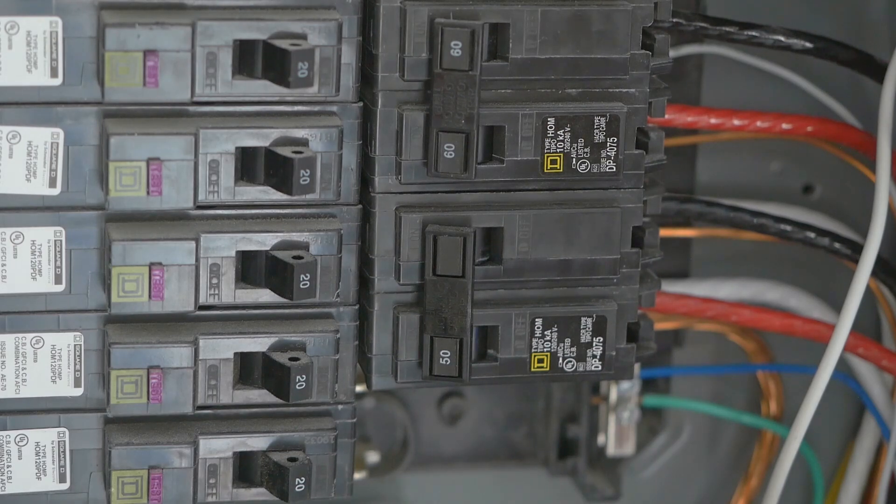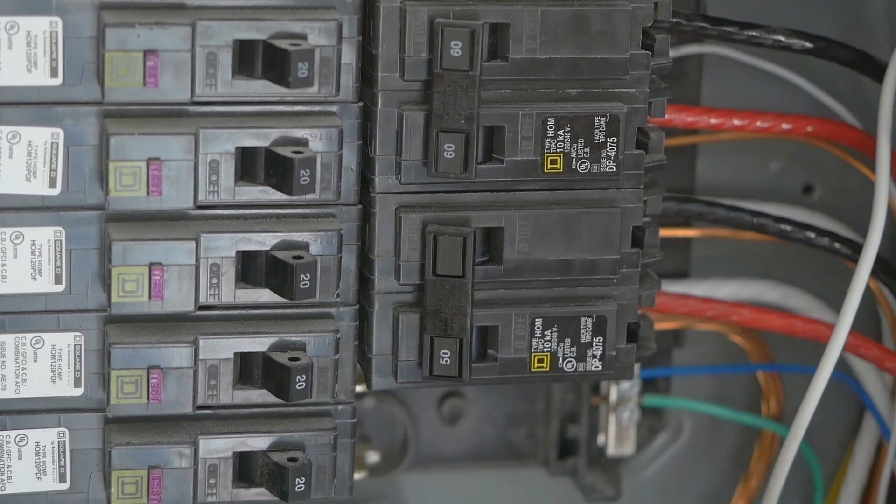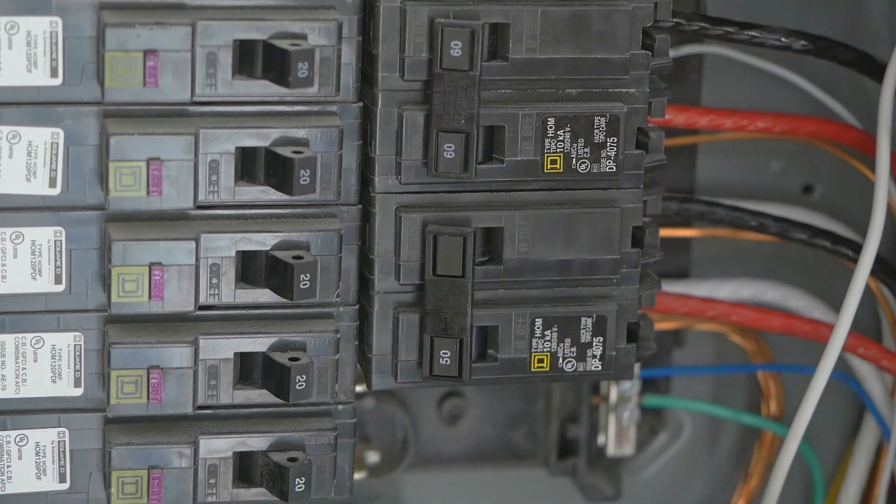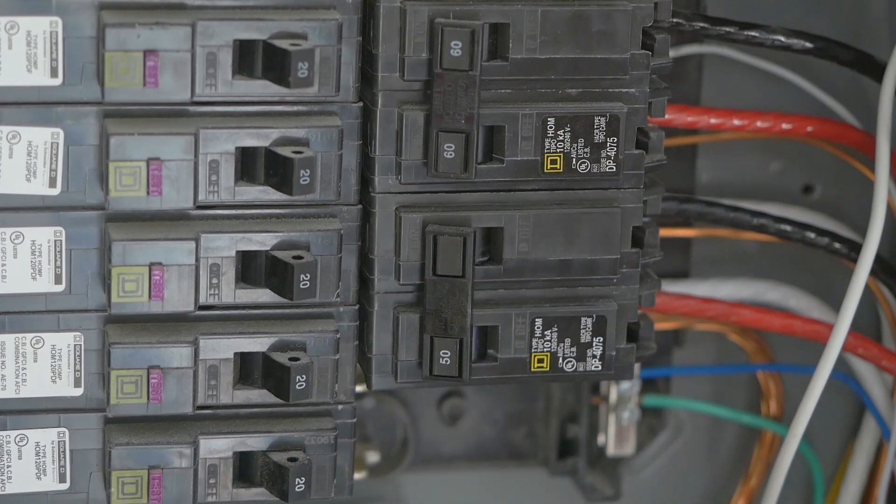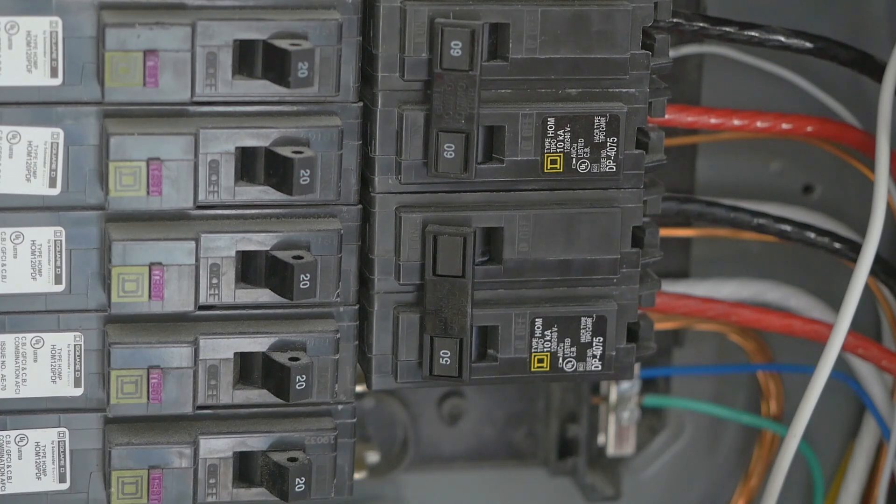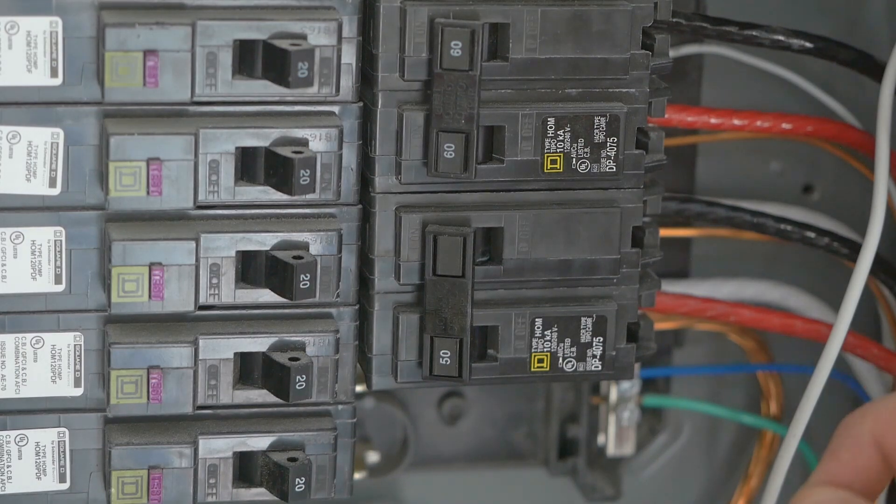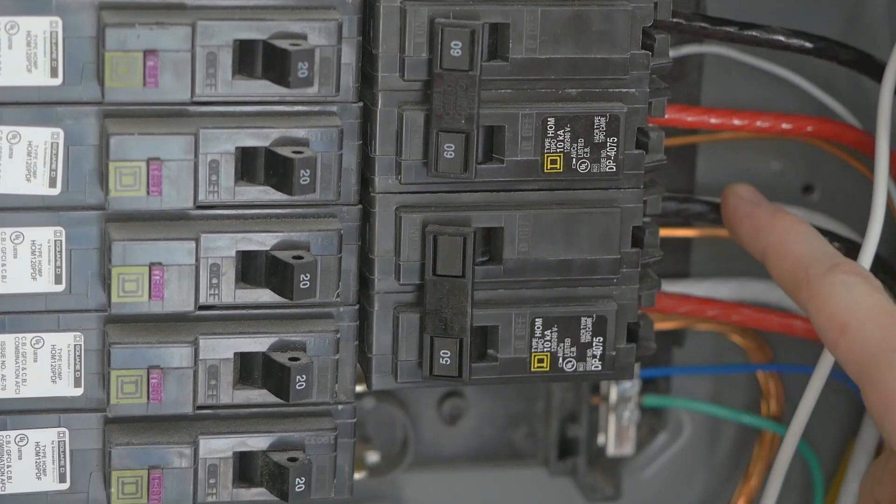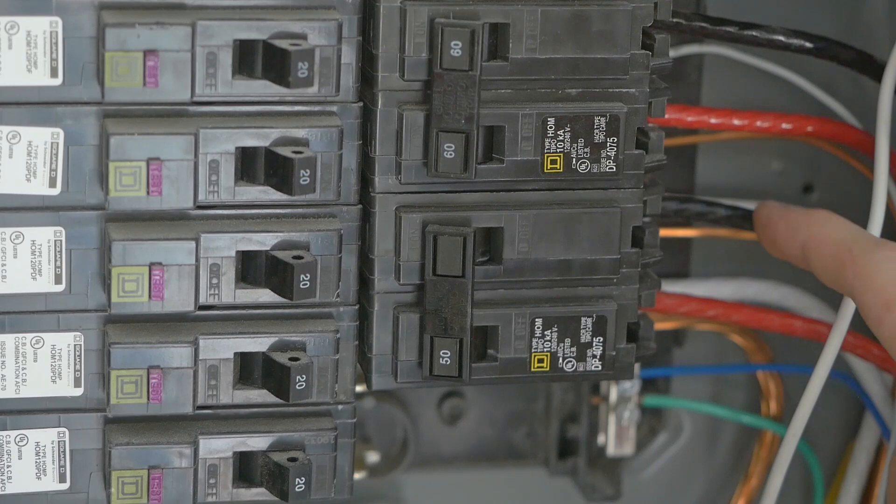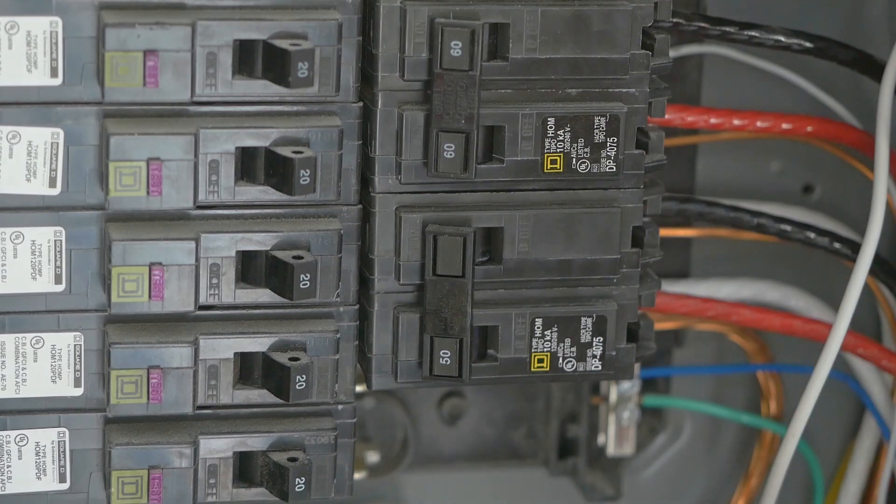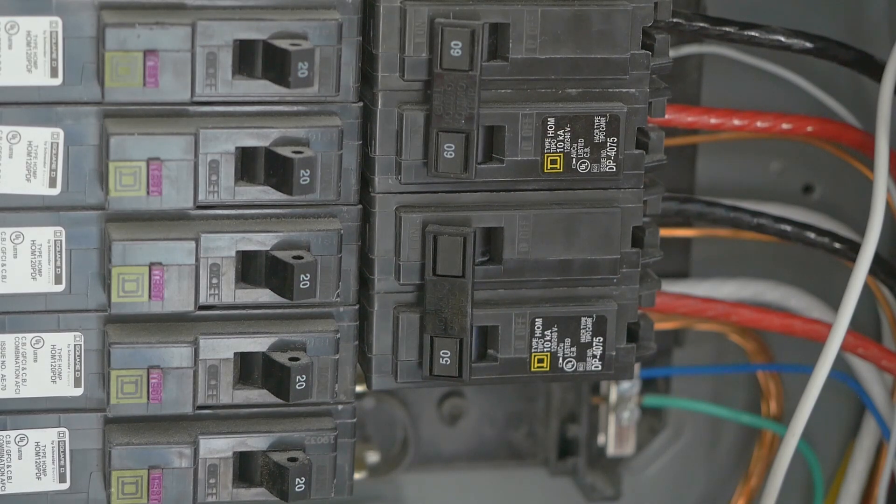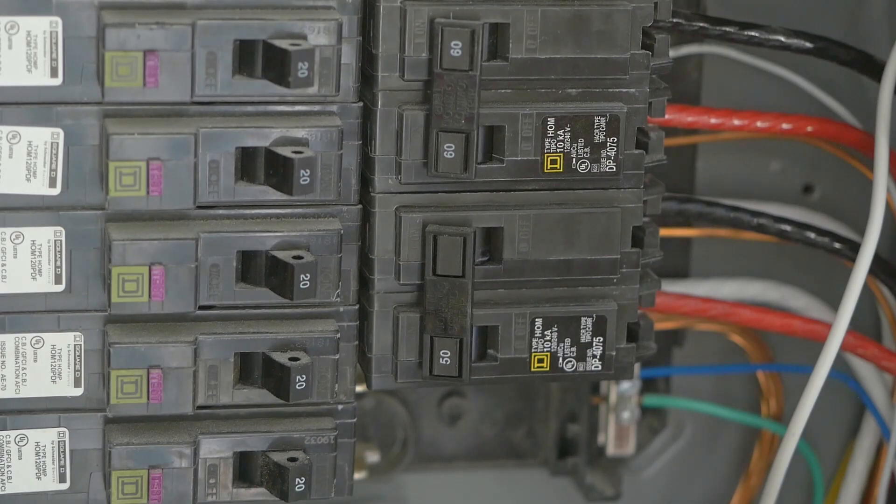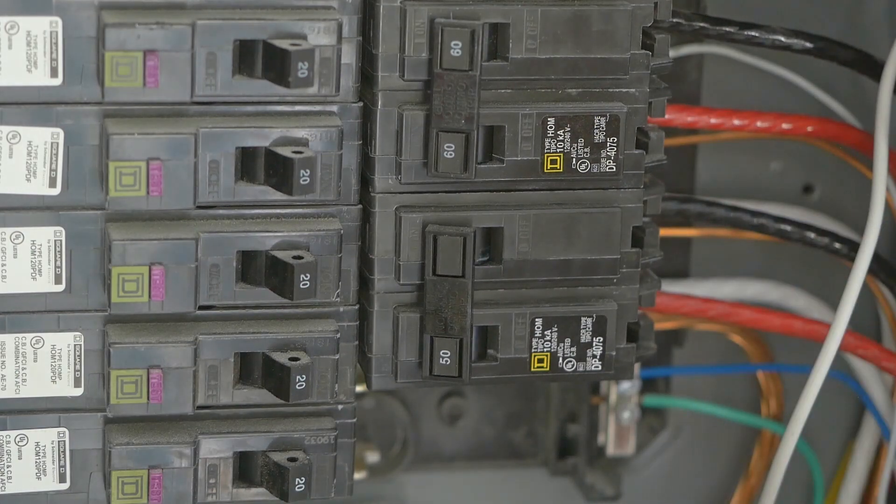The reason it's a little confusing is because it's a mixed 240/120 volt circuit. So essentially this 50 amp breaker plus a neutral feed a sub panel in the backyard which does have some 15 amp 120 volt circuits on it, plus the 240 volt air conditioner. Meaning that the amperage coming out of each of these legs could vary. So I'm not exactly sure how the app is going to compute that. Theoretically each of these two would need to be computed separately and then mathematically combined. I'm sure it's not that uncommon of a situation where you essentially have a mixed voltage circuit. A lot of appliances run 120 volts and 240 at the same time, so I'm just going to clamp it on each leg and hopefully the app is smart enough to be able to set that up.